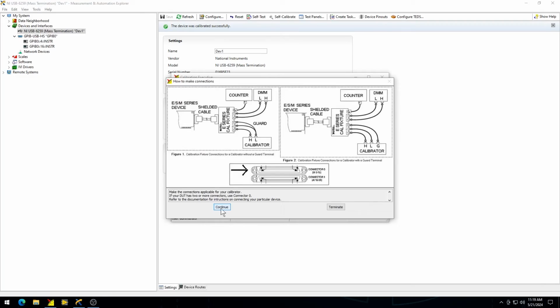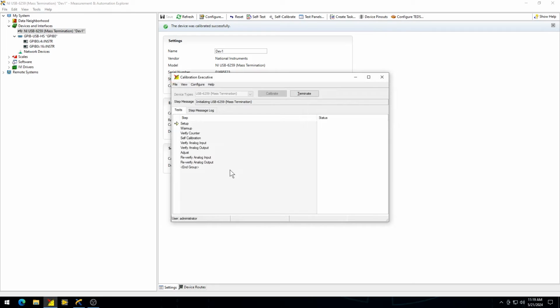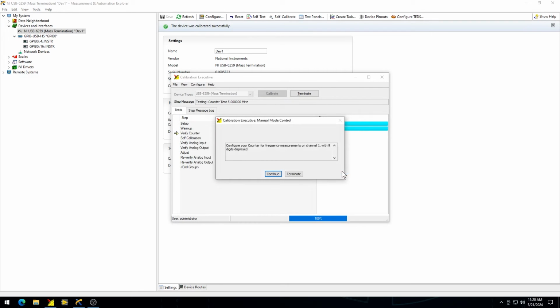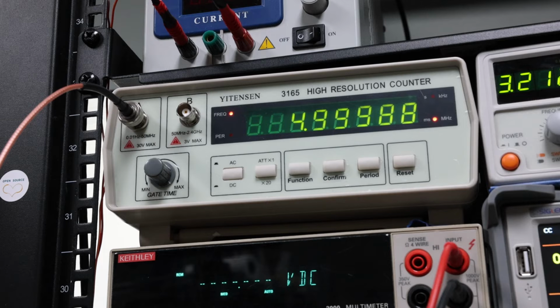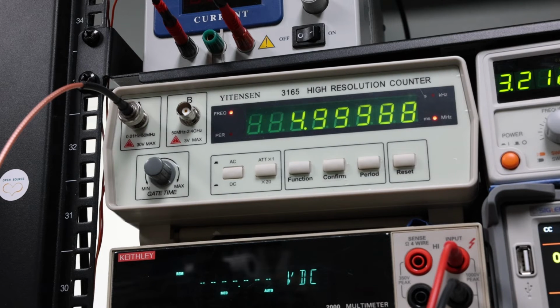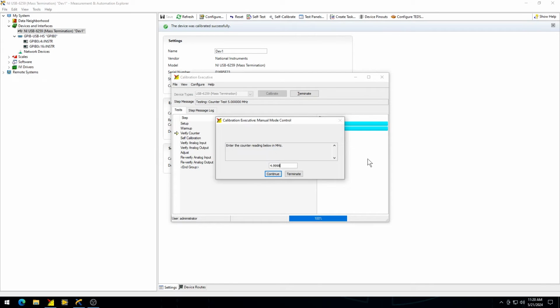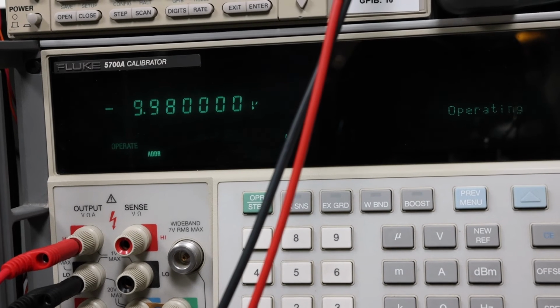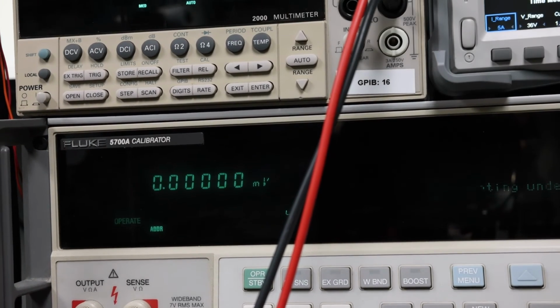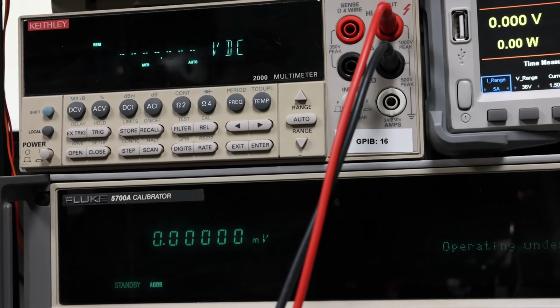Proceed with calibration. Click Continue in Calibration Executive. Enter the counter reading in megahertz when prompted. For example, if the reading is 4.9998 MHz, record that number. This is when the analog input and output get verified.